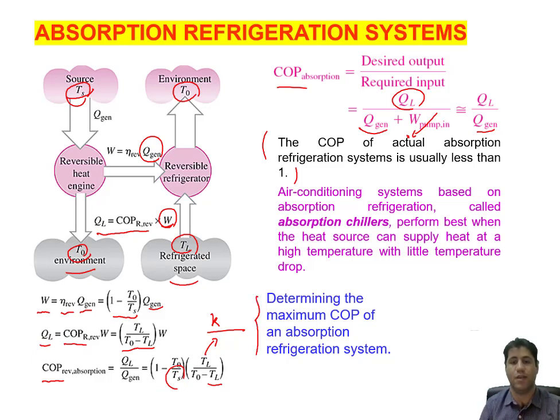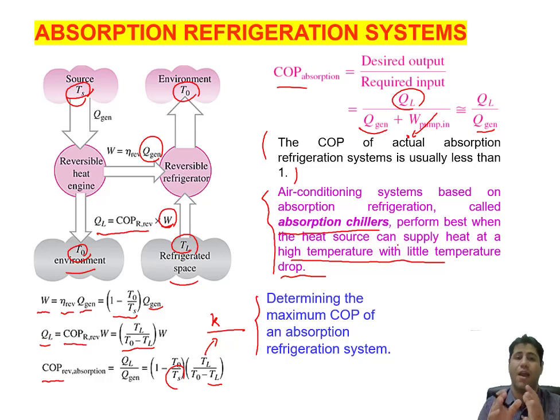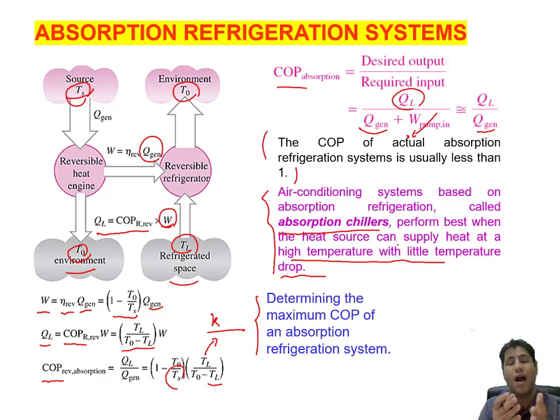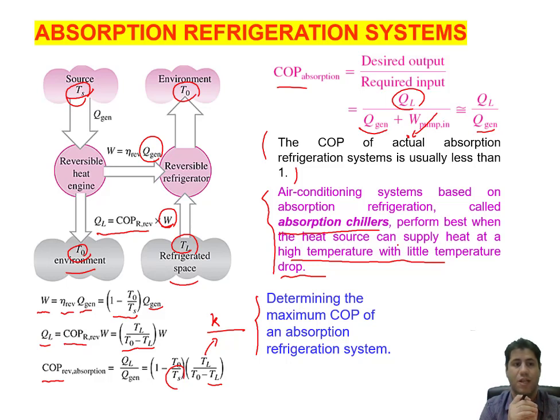Air conditioning systems based on this absorption refrigeration system — also called absorption chillers — perform best when the heat source can supply heat at high temperature with a small temperature drop. The higher the heat source temperature T_S, the higher the COP. With this, we reach the end of the chapter — this is the last type of refrigeration system introduced.